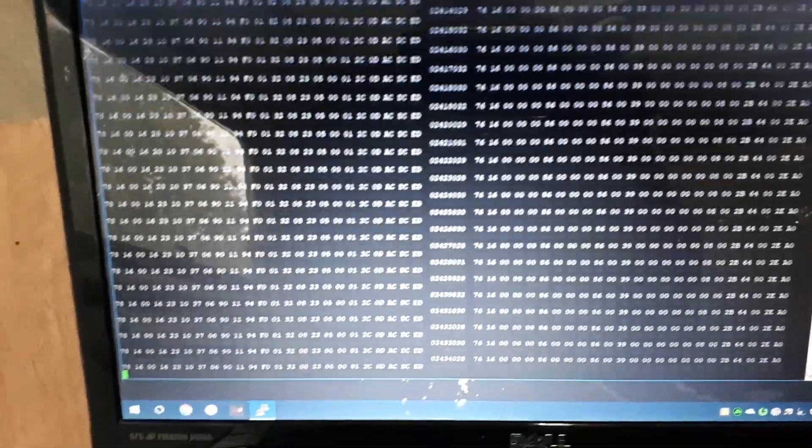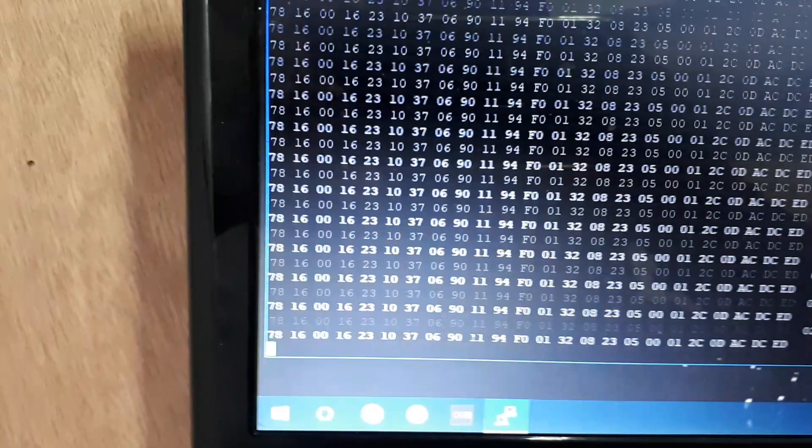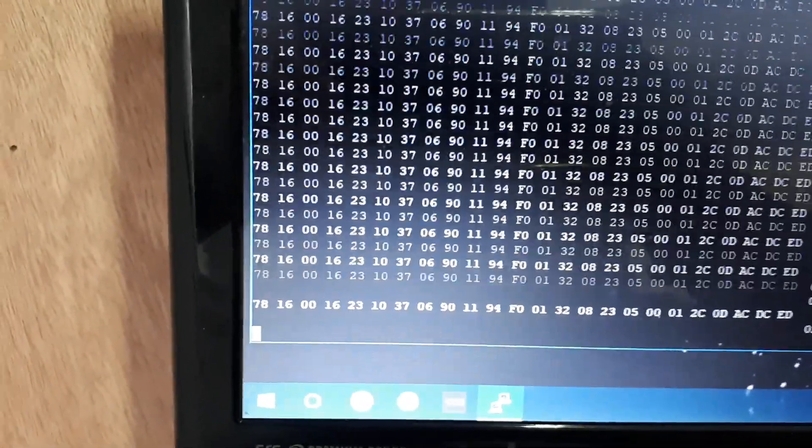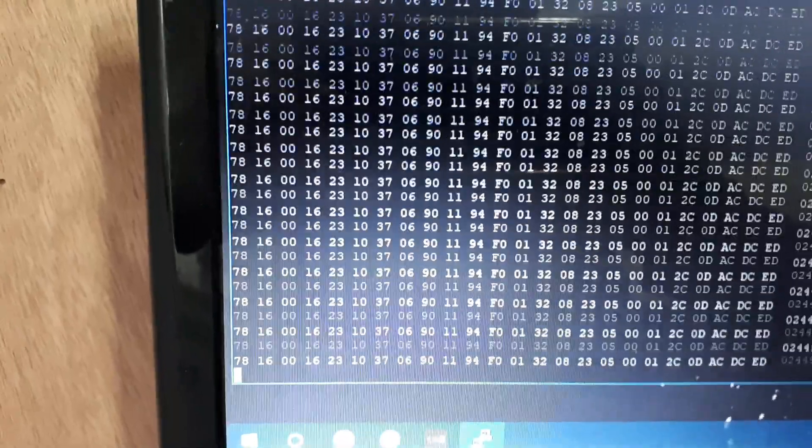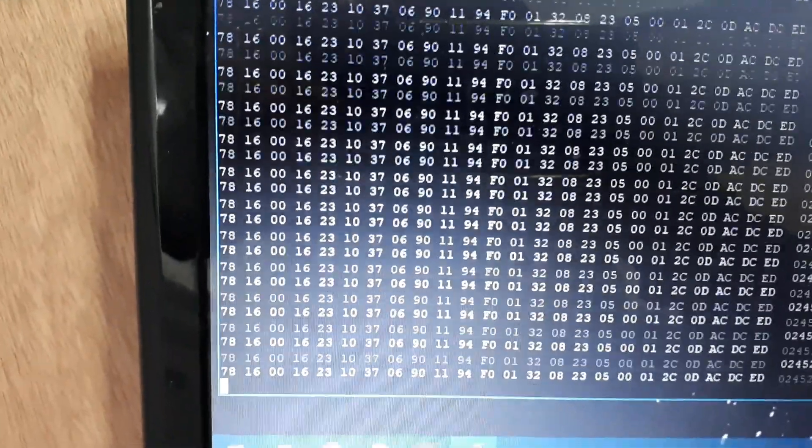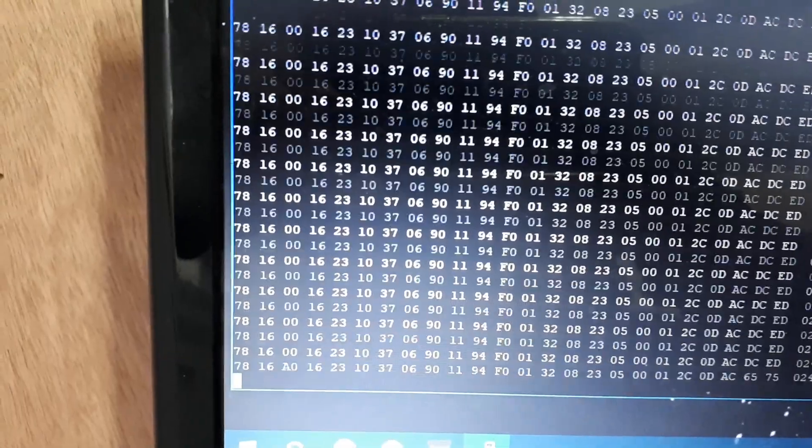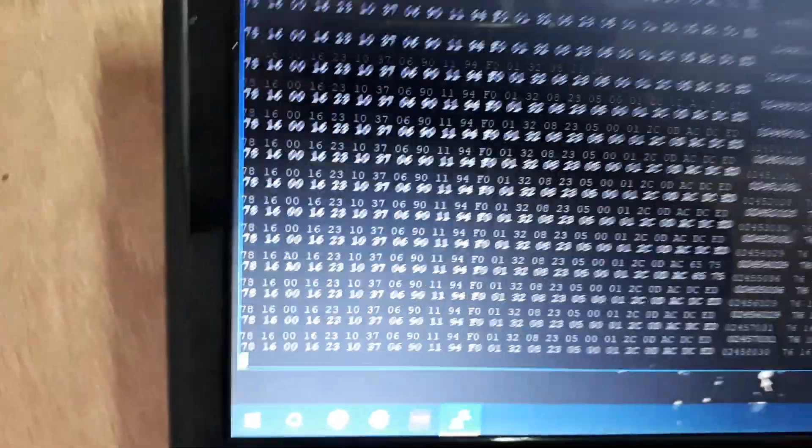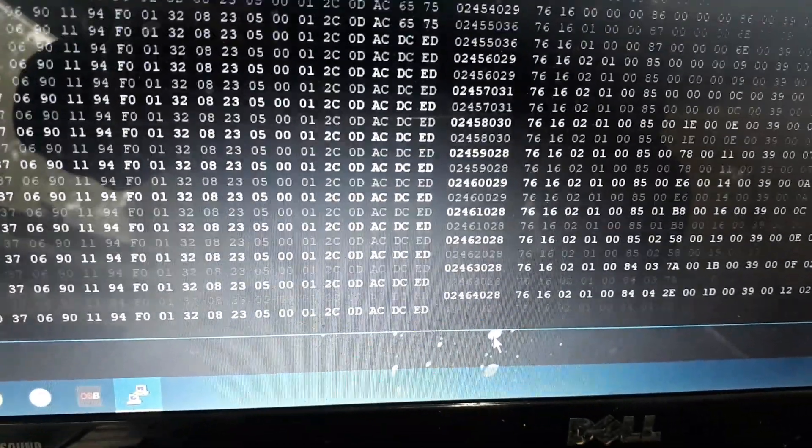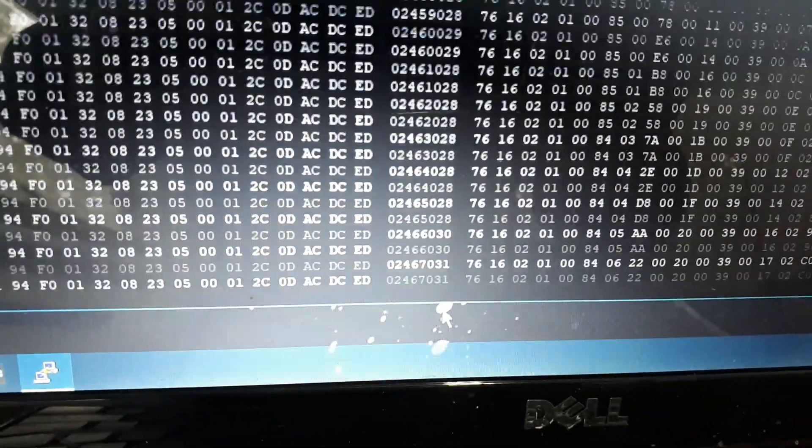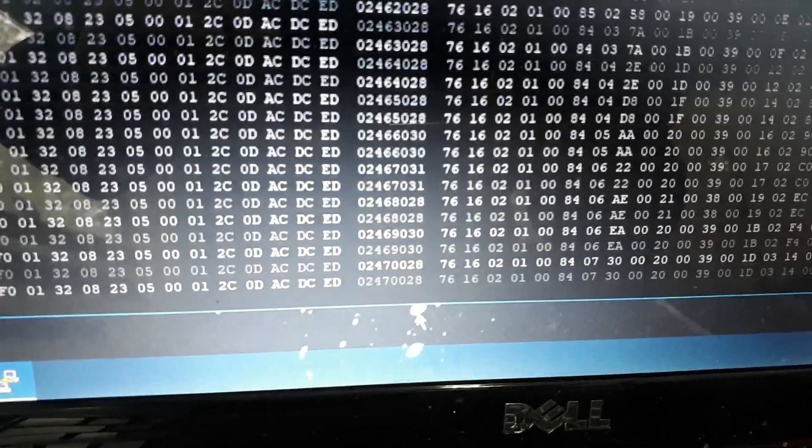Now I can demonstrate turning on the heater. I hit the plus key and over here we'll watch - if we watch that first byte - that third byte is the command value, so you just need to send the value A0 momentarily for one cycle and that's enough to turn the heater on. There's a click of a relay. The fan's caught up on something. There we go. The 0201 in the third and fourth bytes over here show the heater is actually up and running.